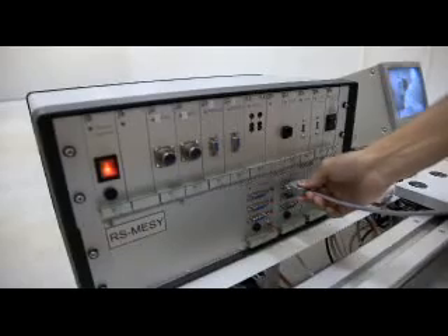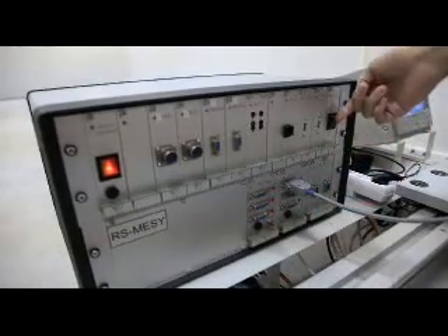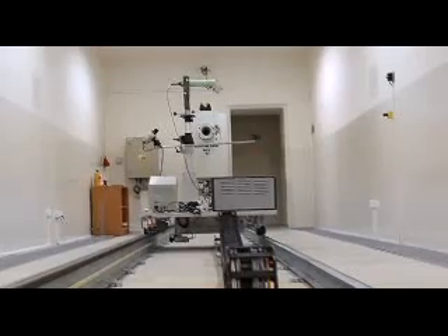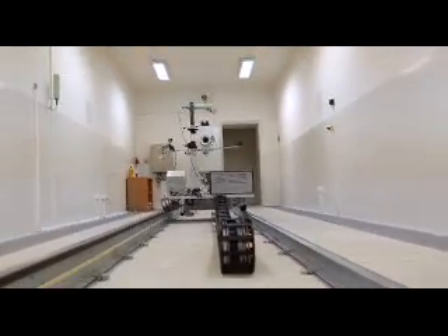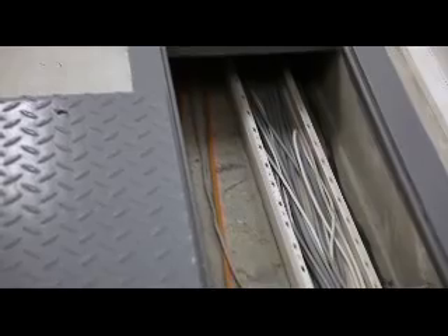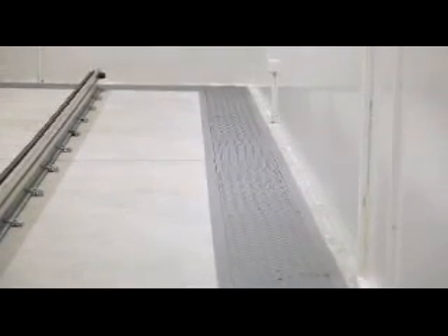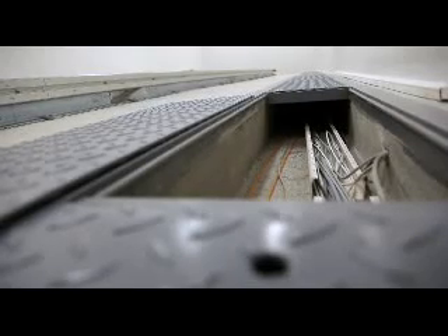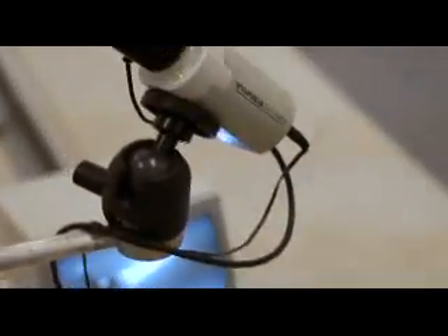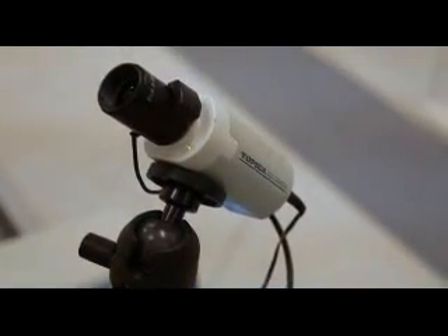The operator, where possible, connects the calibrated instrument with the control room through the interface on the calibration bench and cables. Instruments with atypical outputs can be connected via suitable temporary cables directly to the control room, utilizing the cable channel in the floor. When an instrument is unable to share data electronically, the operator will use the camera to be able to view its display from the control room.